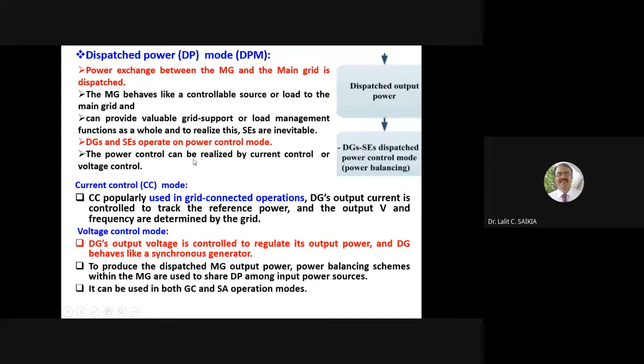Dispatch power control mode I already told. In standalone operation, the power management and control strategy is focused on the microgrid AC voltage and frequency control as well as demand power sharing among DGs and SEs. Various schemes have been proposed to realize this. The droop method is most common. The droop method emulates the behavior of a synchronous generator, where voltage and frequency vary with the output P and Q of the DG. Here the output P and Q of each source is determined in order to regulate the frequency and voltage of the AC bus at their desired values.